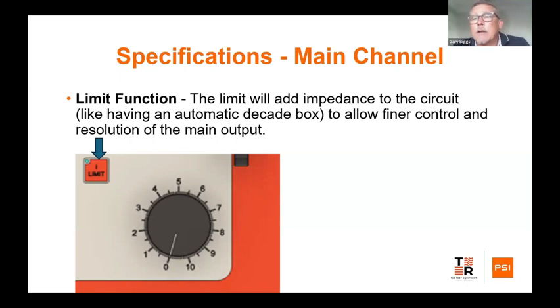Any engineers listening today will be familiar with the fact that you quite often carry resistor packs with you, so that you can add extra burden into the circuit and thus give you a greater amount of control. What we've done is put a little limit button on our units. When we hit that limit button, it is like adding resistance into the circuit, so we get finer control over the output current that we're trying to inject, and that gives us a much better resolution and a much better control over what we're doing for these low burden digital type relays.